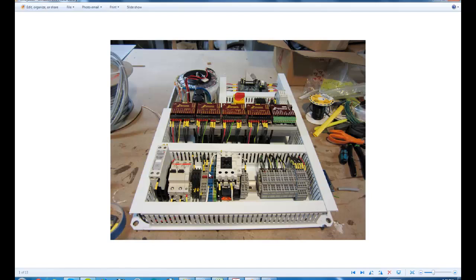And then scooting over here, this is the main AC contactor for the entire panel. I'll explain it when I go back up to the door harness. But basically, this turns power on to the entire panel, front end of the breaker, and this takes the load. The coil is actuated with a momentary push button switch. It's also a double push button switch, which you'll see in another picture, green and red.